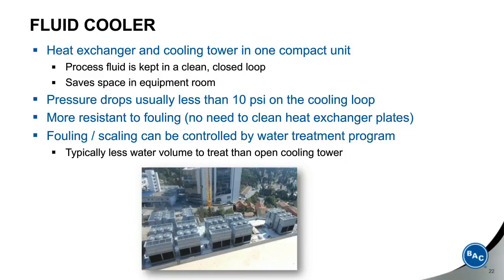Another consideration is that because the spray water stays within the unit and doesn't have to be piped to an external heat exchanger, the open loop water volume is usually less in a fluid cooler than it is in an open tower. And as water treatment costs are proportional to the system volume, that would imply that the fluid cooler is less costly to treat.